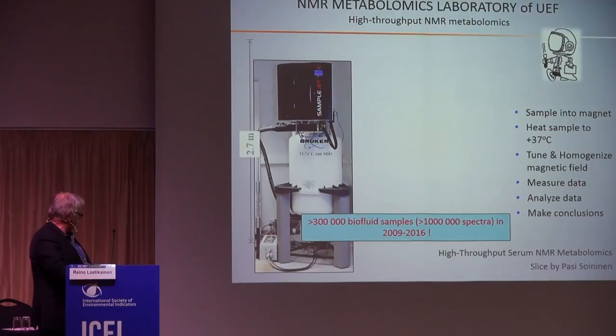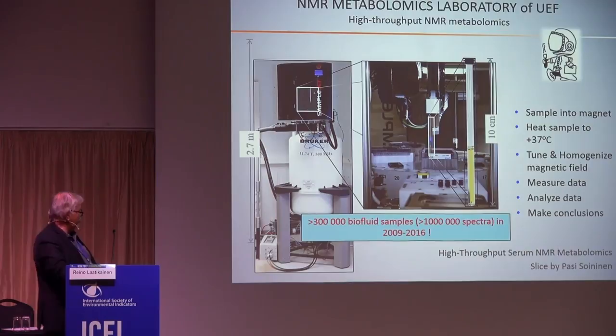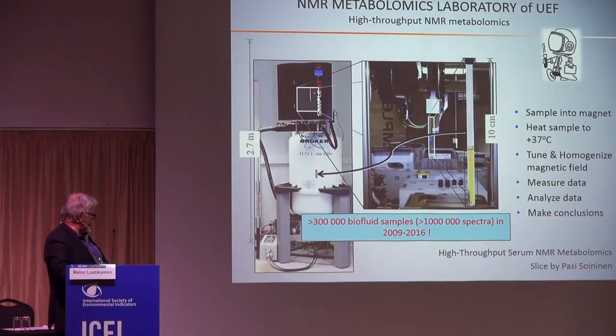This is how an NMR spectrometer looks like. The NMR sample is put into the spectrometer. First you put the sample in the magnet, it is heated quickly to a stable temperature, and then the automatics perform the magnet shimming operations.